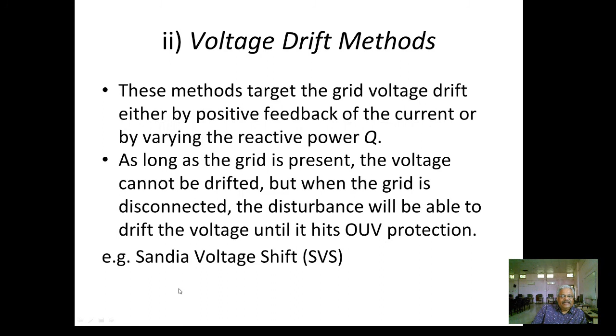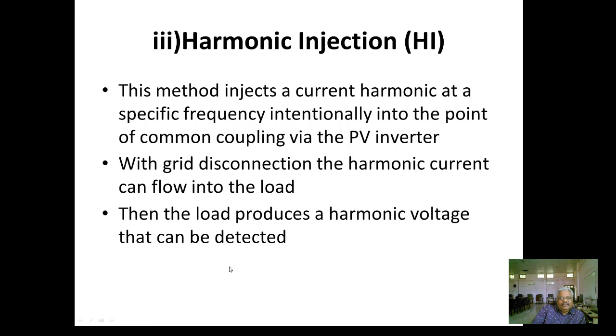Third is harmonic injection. This method intentionally injects a current harmonic at a specific frequency into the point of common coupling via the PV inverter. With grid disconnection, the harmonic current can flow into the load. Then the load produces a harmonic voltage that can be detected. The harmonic current, when it passes through the load, generates a harmonic voltage, and that can be detected for the anti-islanding situation.